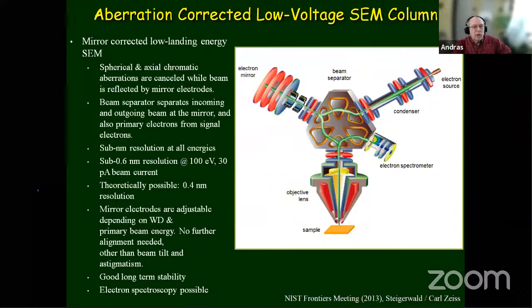So aberrations are significantly improved at low energy operation. Chromatic aberration is one of the problems. So either someone chooses an electron optical or electron delivery system like this, or uses a trick that FEI uses, for example, for low energy operation, when right at the beam exit, when the electrons fly out of the cathode, they move the beam to the side and use only a small portion of the beam on the skirt where the energy variation is much smaller.